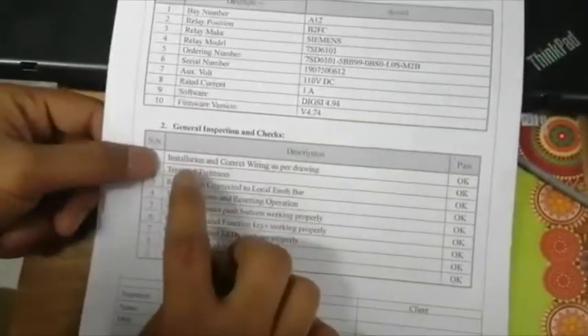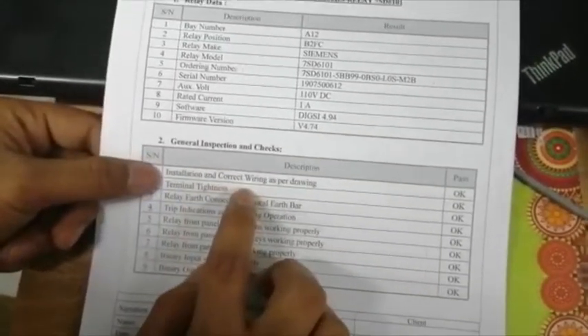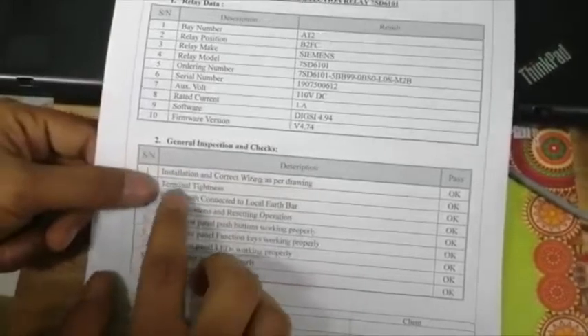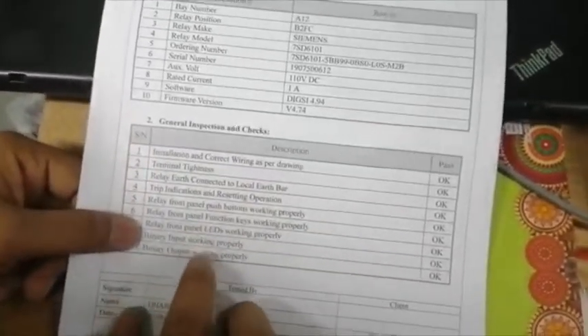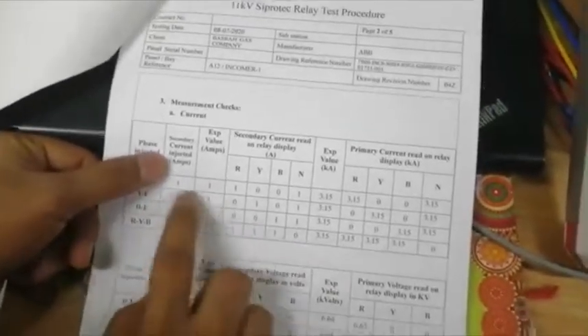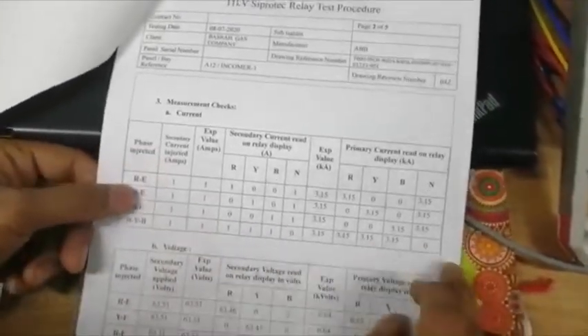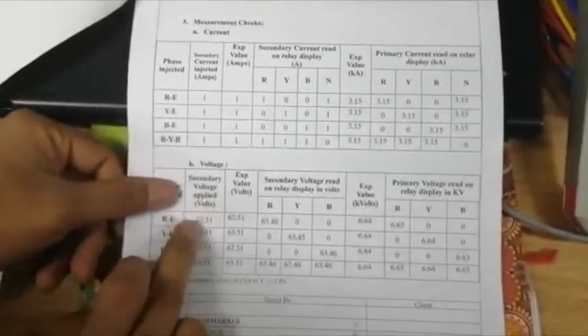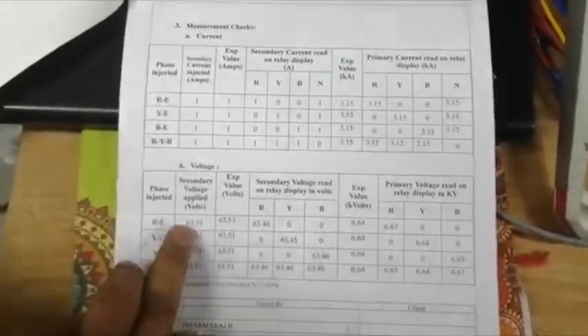This is our test report, test procedure. I just filled these details, and our first test: installation and correct wiring as per drawing. Terminal tightness check here, and hardware test. In hardware test, BI, BO, and LED I have checked. Next measurement, I just injected 1 amp in secondary side RYB, and respective value noted here, and same voltage 63.5 volts injected in secondary side, and the voltage is noted here.